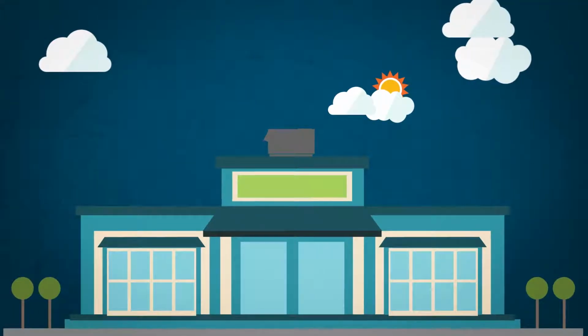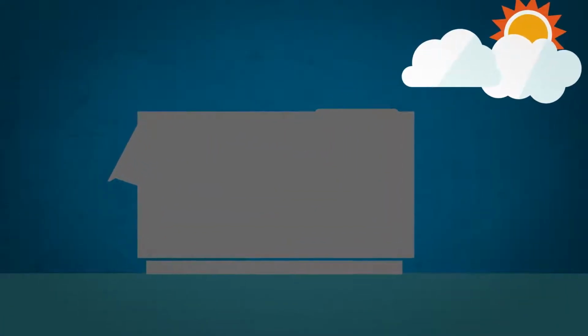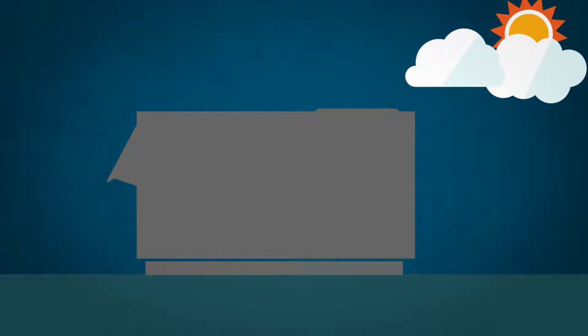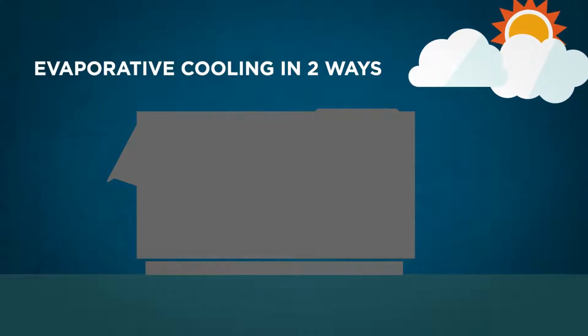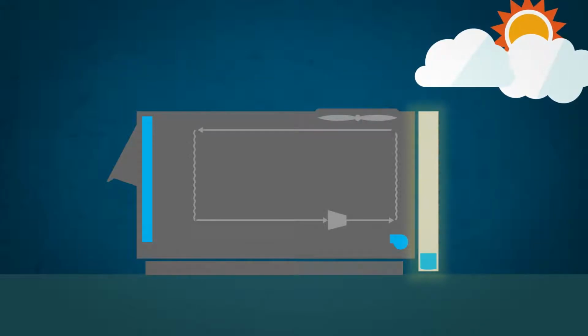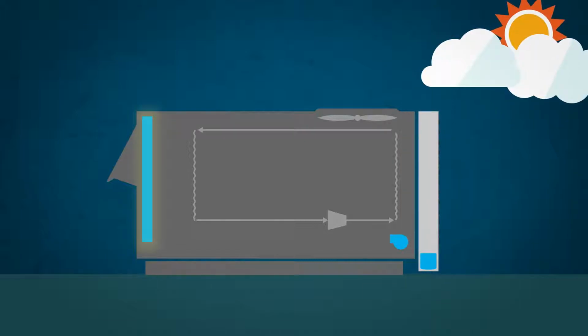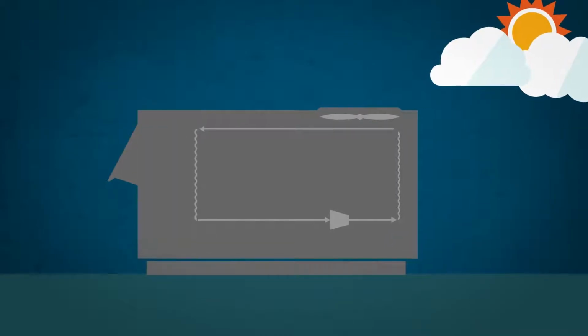DualCool is designed as a retrofit for existing commercial rooftop air conditioners. DualCool uses evaporative cooling in two different ways, hence the name DualCool. Number one, it improves the efficiency of the vapor compression cycle, and two, it reduces the ventilation cooling load. Let's explain that a little further.